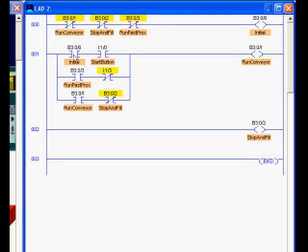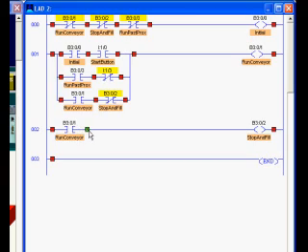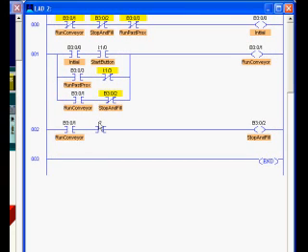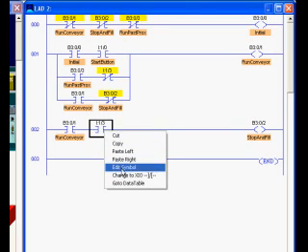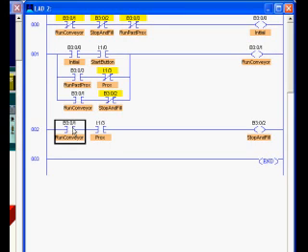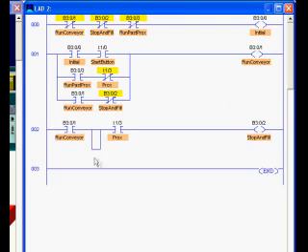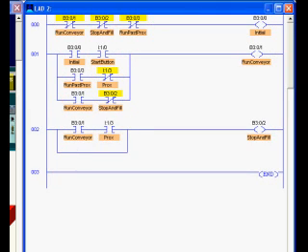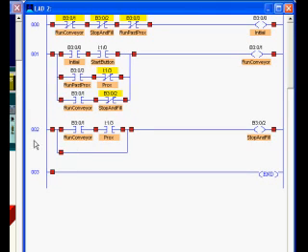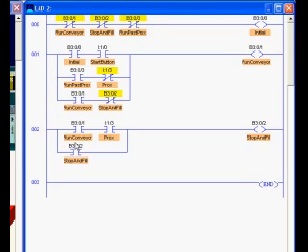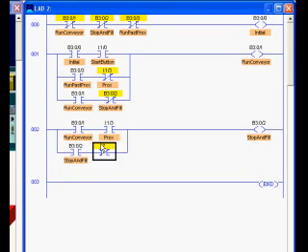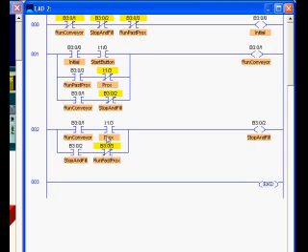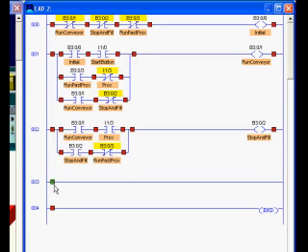So now let me build up B3:2 put an output for B3:2 the same thing. Where do we come from? We come from B3:1 so let's put that contact in there and what condition gets us there. And that is the proc switch. So that is the only arrow going into this step. So now it's time to add our latching branch. Now in our latching branch once again normally open contacts with the same address as the output so B3:2 and we're going to put normally closed for the steps that we were going to which is B3:3.